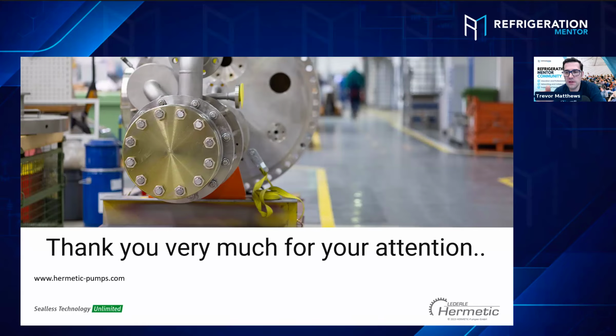And there's another question here. I think you answered about the maintenance schedule and the manufacturer's manual. You say if it's running good, amps are good, flow is good, do not open it. Don't touch it. Don't mess up the pump, because most of the problems come when people say I want to open the pump, and after I close it back, it's a problem. Leave it run.